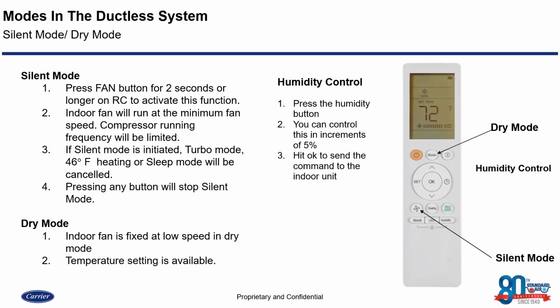Now the next mode on there is going to be our dry mode, which essentially is on the older style, what I always call a poor man's humidity control. What you're looking for when you hit the mode button is a little water droplet. And what this does essentially is gets the cooling to whatever set point that you have, but it's going to keep the fan speed at a low speed in order to produce a colder coil.